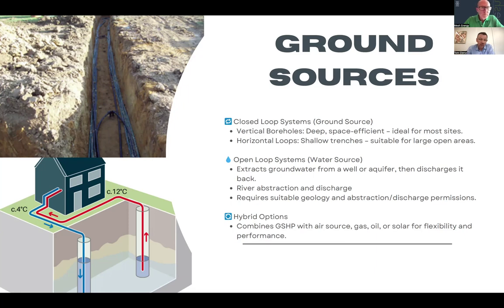The picture on the bottom is an open loop system, where we are extracting water from the water well. There is a pump in the extraction or abstraction well. We are pumping actual water from the aquifer into the heat exchanger unit, and the heat exchanger takes the heat from the water, and the water is then discharged to a discharge well. So that's an open loop system. We can also do a system where we are extracting from a river, lake or pond, depending on the size. That is very common if commercial properties are near lakes, or the Thames in London, because that reduces the drilling aspect of the system. It involves a bit more Environment Agency input on the permit side, but it works out potentially slightly better.